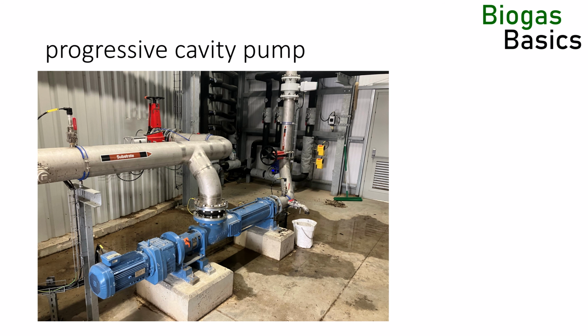And now, pictures. Progressive cavity pumps are the workhorses of the AD industry. They are used for medium and high viscosity applications and media with yield stress. Progressive cavity pumps can handle fibrous material.